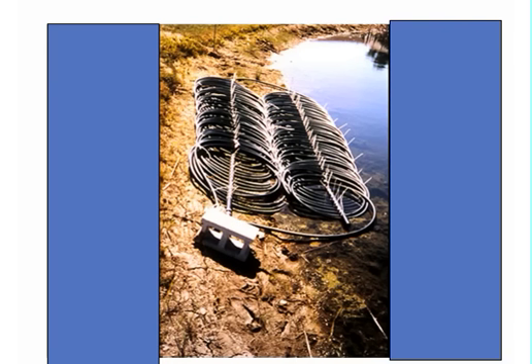Here's another example of a slinky loop. Some guys do variations of their own. This one is lacking any kind of framework. I know a lot of people put a PVC frame, like what you saw with the slinky coils. That's just fine, keeping it up out of the mud and evenly distributing that weight so it stays on the bottom, along with your manifolding. Make sure your ability to disperse flow evenly and properly is maintained, as well as, I want to emphasize, good design conditions so you're able to purge the air out of the loop. That's a critical component of every geothermal closed loop design.